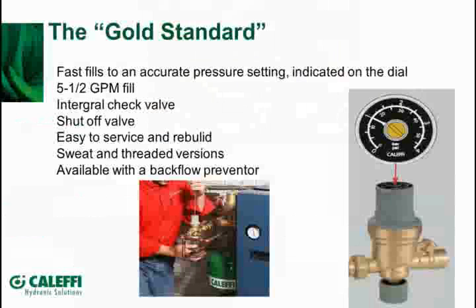All right, now let's talk a little bit about fill valves. So far we've talked about systems where we're going to pump the glycol with a hand pump or some kind of powered pump. But now if you're filling a system with just basic water from the job site, you want to have some kind of valve that's going to not only fill the system up quickly, but also maintain the pressure. As air eliminates out of the system when you first fire it up and the boiler heats up, certainly some of that air is going to come out of the solution and vent out. And of course you want to replace that with fluid so you don't have a low pressure condition and have a lockout in your system.